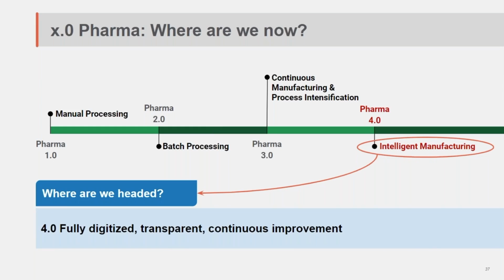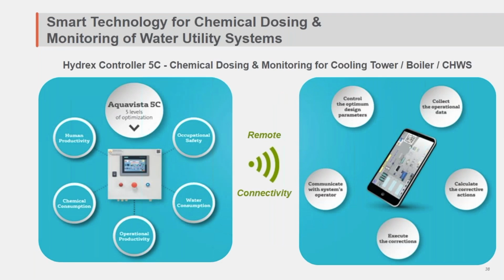And how Veolia will help our customer, or you, to translate from Pharma 3.0 to Pharma 4.0. Firstly, we'll introduce ourselves with the smart technology for chemical dosing and monitoring for water utility system. We have our Hydrex controller 5C, which is used for chemical dosing and monitoring for our cooling tower, boiler, and chill water loops. With AquaVista 5C, we are able to connect it remotely to any smart devices. And with this platform itself, we are able to control the optimum design parameter, collect the operation data offsite, calculate the corrective action, and execute the corrective action as well.